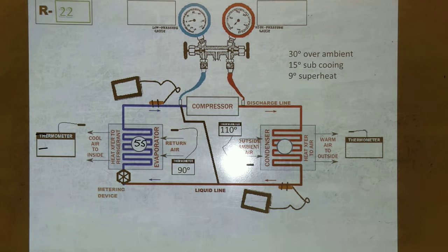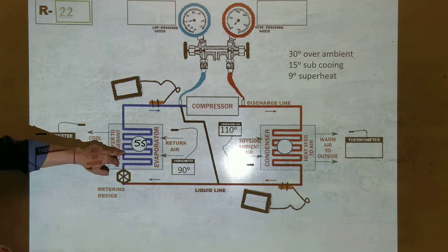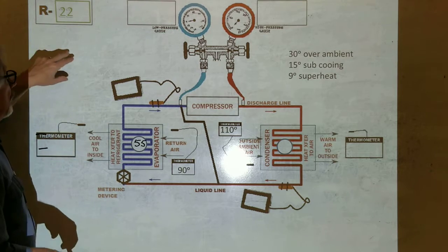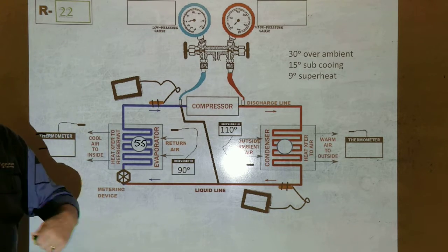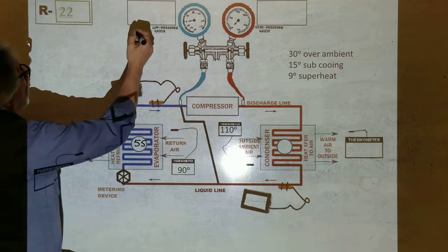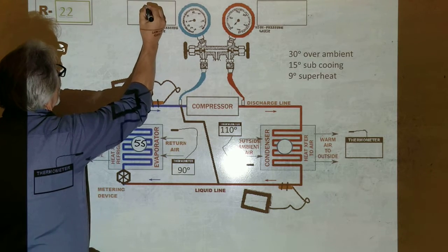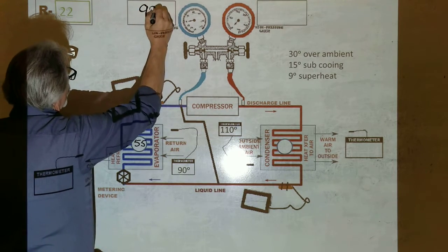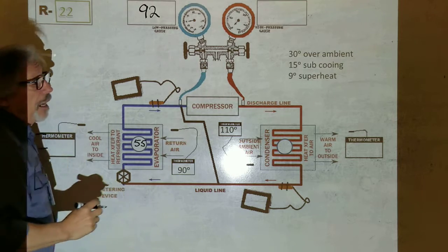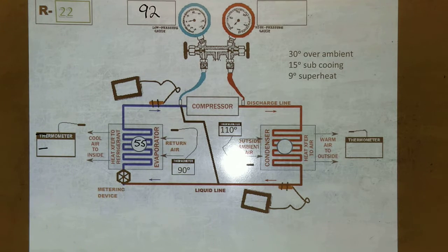So I went to R22, R22, and then I see the PT chart, right? And then what we're looking at is 55 degrees. Oh, wait, I think, yeah. At 55 degrees, R22 is what pressure? 92.4. No, it's 92. You did 55 and then... okay, so 92 PSIG. Okay, go to the...